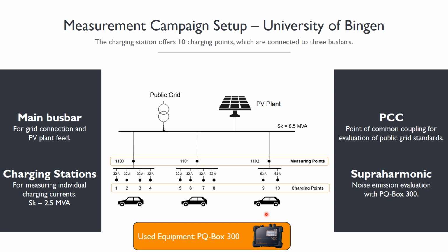We used the measurement points at the main bus bar to evaluate power quality according to public grid standards, and we also used measurement points deeper in the grid to measure supraharmonic noise and the interaction of different vehicles during the charging process.